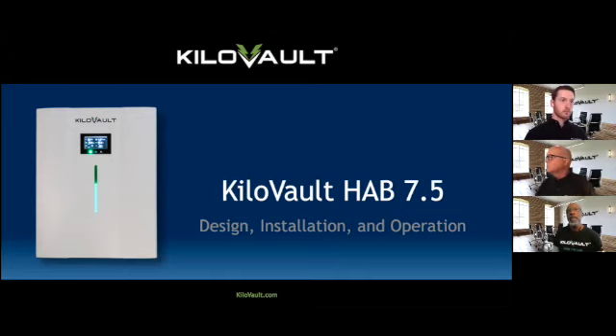And is showing a different value than what you're seeing for the other batteries that are at the same voltage. If you wish, you can go ahead and do another recalibration in order to try to get it back in line. But that state of charge that's being displayed is for us humans to look at. The actual HAB itself is operating on the battery voltage, the amount of current in and out, and internal battery temperatures. The BMS is making decisions based on that. It's not making decisions based upon the state of charge that is displayed on the display or through the app.